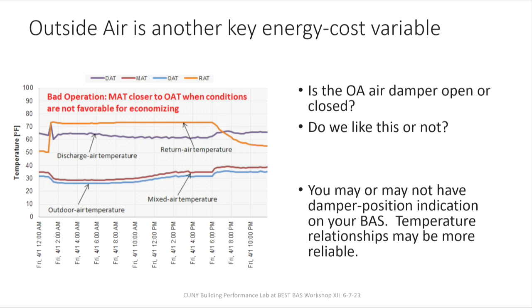Now, if the outdoor temperature were 50 degrees, would we like the outside air damper open? Lots of thumbs up. Right, because we're getting into economizing. So if we're doing any cooling at all, then 50 degrees outdoor air is what we want, and we would like to see it open. So again, these graphs serve multiple functions, and Robert, thank you for that point regarding the freezing hazard and the need for an alarm or even shutdown.